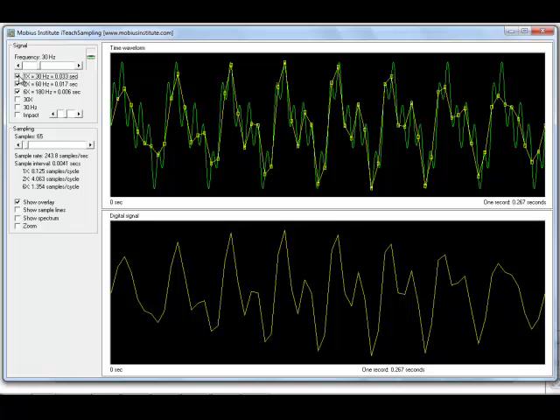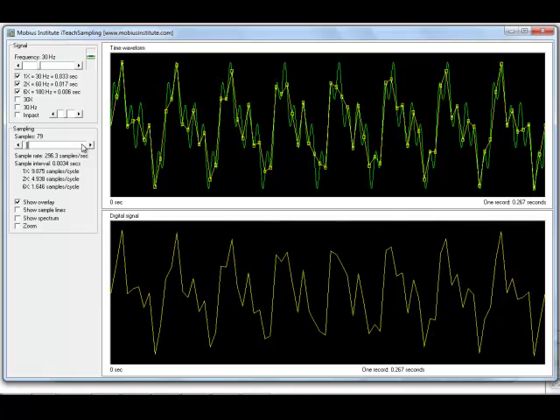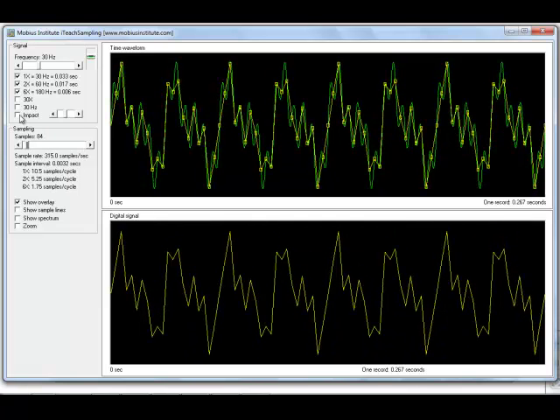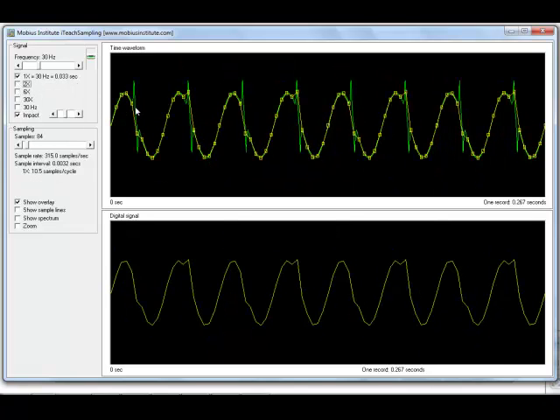From a time waveform analysis point of view, we're interested in how many samples per cycle of all the signal components we're interested in. With this simulator we could spend a lot of time on this, but I can also simulate an impact. Now I've got a little impact — once per revolution in this case — which could be a looseness fault. Something happens each time the shaft goes round, but we can't really see it in our time waveform, so we obviously need to sample at a higher rate.